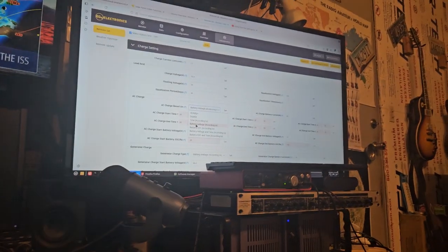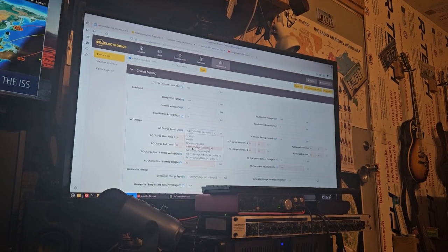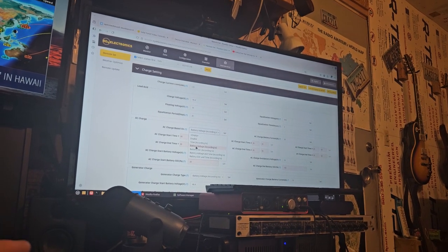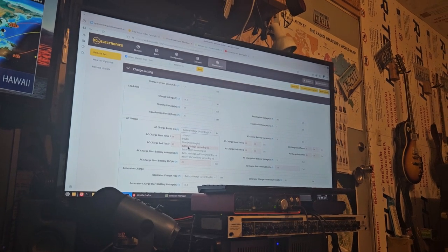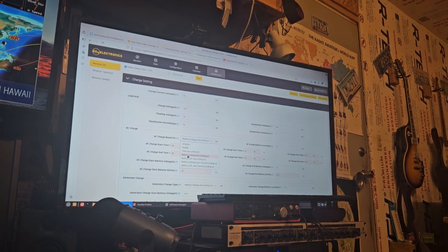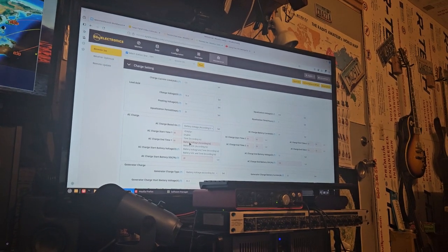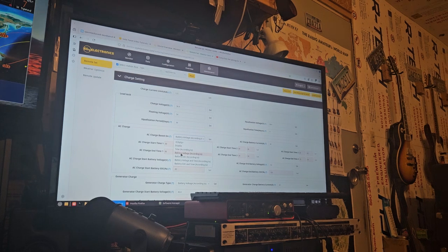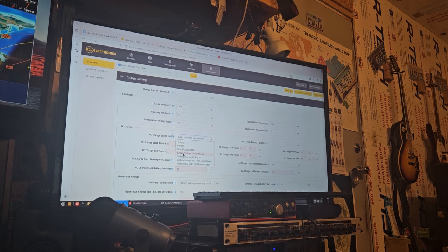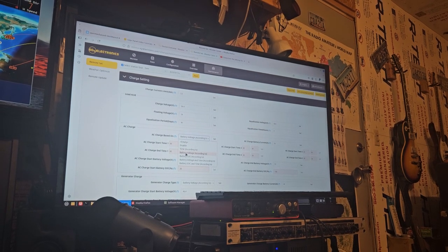I just want it to kick on when the battery voltage gets to a certain point, so we can keep the system completely charged all the time, so the battery never goes into cutoff, and whatever critical loads are on this inverter will always be on 24/7. Traditionally, I would just run it until it hit the low voltage cutoff set on the inverter, and I'd have it cut off really high at like 51 volts, which is like... probably 48 is like 10%.